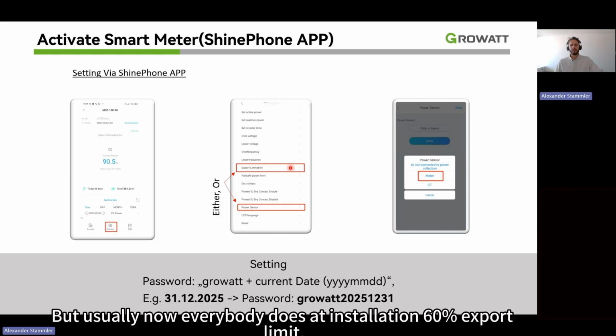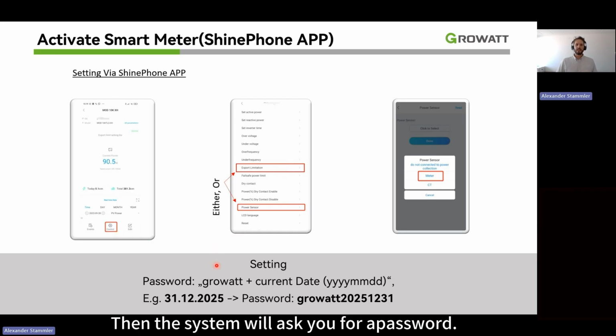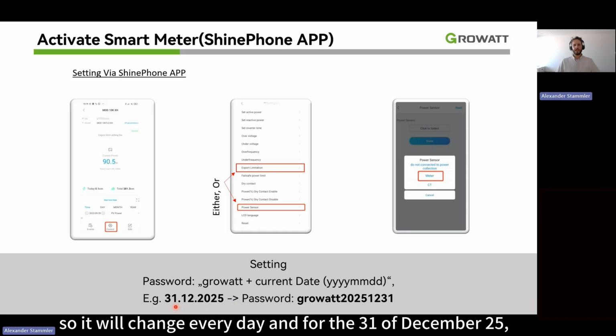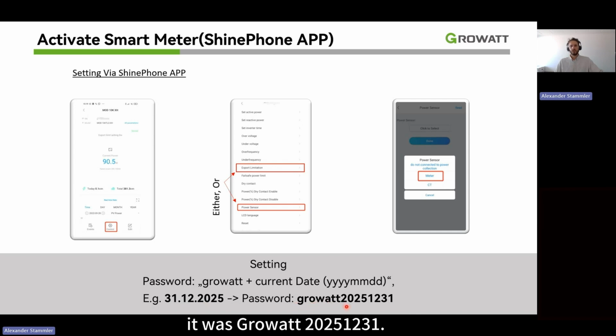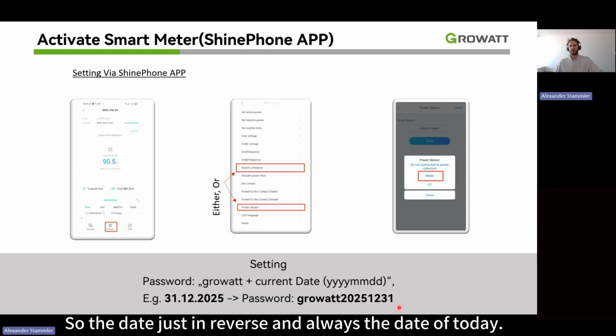But usually now everybody does at installation 60% export limit. Then the system will ask you for a password. The password is always depending on the date, so it will change every day. And for the 31 of December 25, it was Growatt 2025-1231. So the date just in reverse. And yeah, always the date of today.